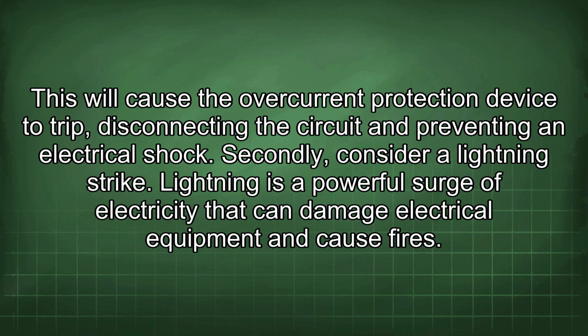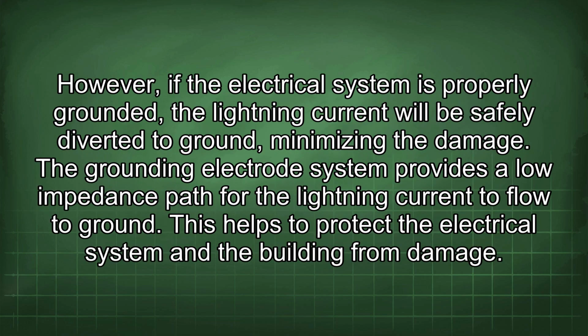Secondly, consider a lightning strike. Lightning is a powerful surge of electricity that can damage electrical equipment and cause fires. However, if the electrical system is properly grounded, the lightning current will be safely diverted to ground, minimizing the damage. The grounding electrode system provides a lower impedance path for the lightning current to flow to ground. This helps to protect the electrical system and the building from damage.